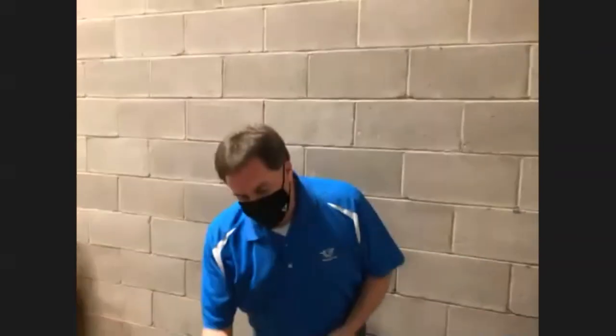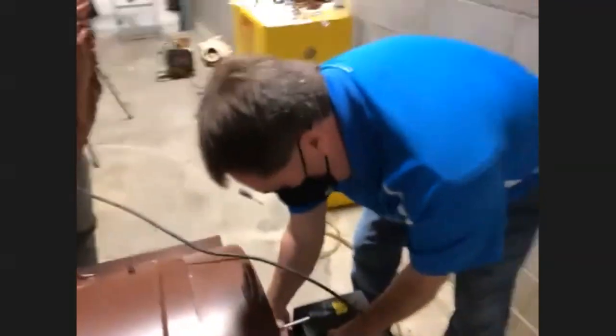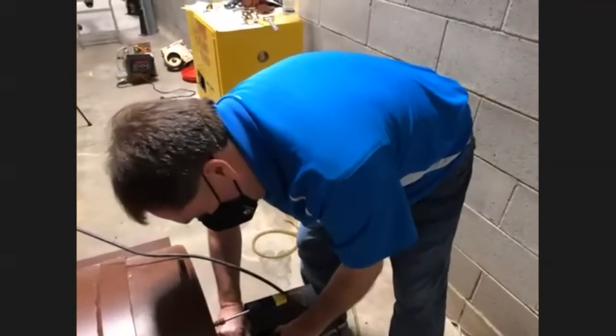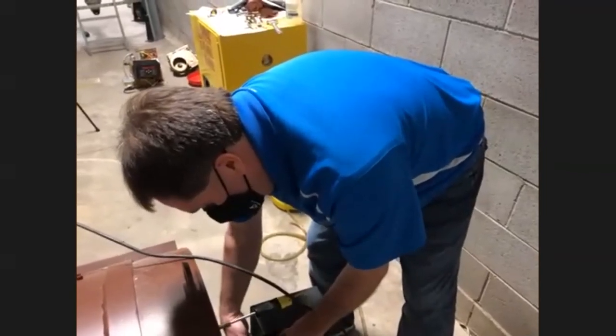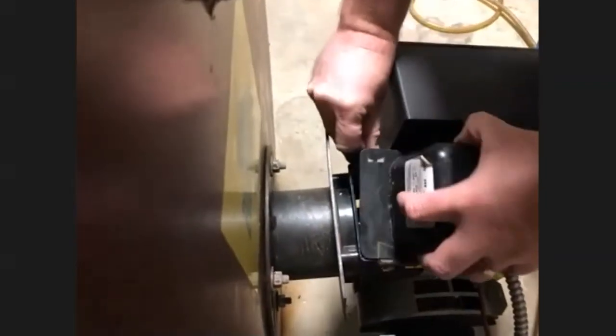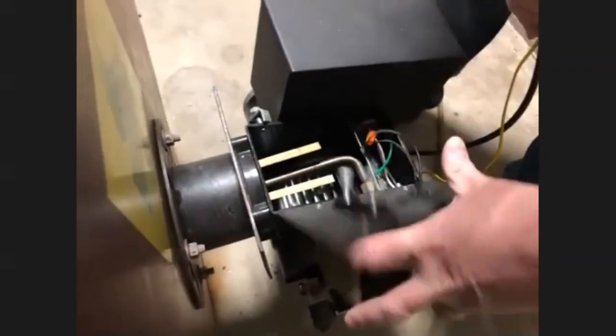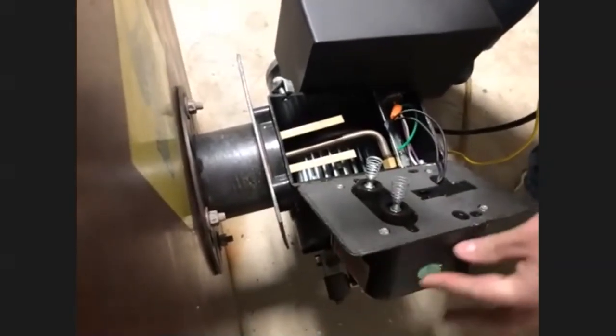If you do not have spark, you have fuel spraying in there, but you're not getting any spark, chances are you may have an issue with your spark ignition transformer. And that is set up right on top of the burner itself. You have a clamp that holds that in place. So you loosen that clamp up, loosen that bolt up, remove that clamp. This is your whole ignition, your spark transformer right here.